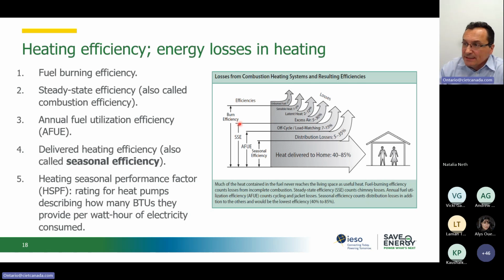So with this, we get to a level where we call this steady state efficiency. This is what manufacturers like to show us, because this is the maximum efficiency that they can show us in controlled environments. Usually they use this under specific parameters, and they can measure it when the boiler achieves a steady state, or any combustion equipment.